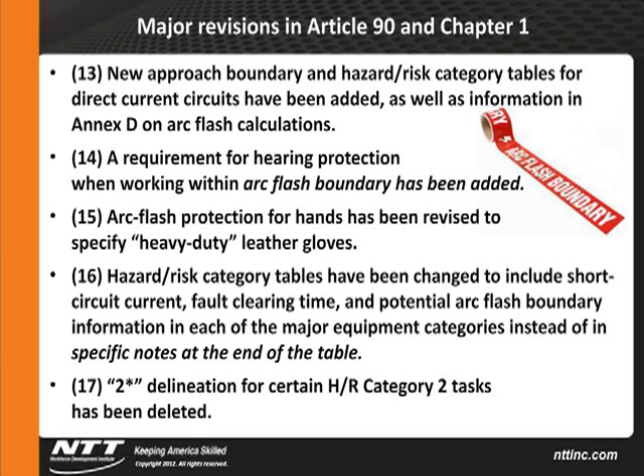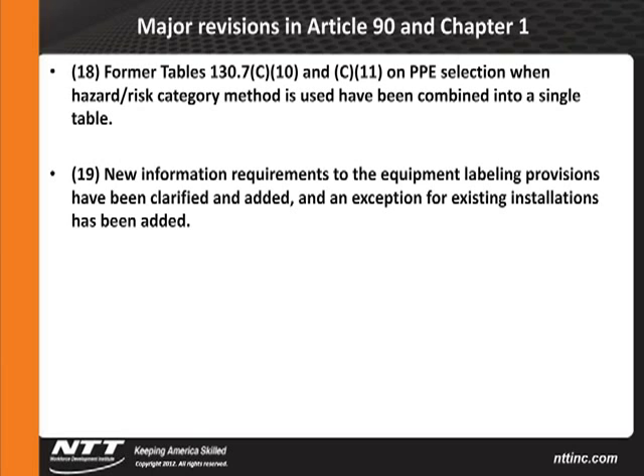Some of the tables have been revised, and we'll get into a few of those. And new information requirements to the equipment labeling provisions have been clarified and added. And there's an exception for existing installations that has also been added. So it's basically said if you have done a calculation in the past, we don't have to go out and change those labels.